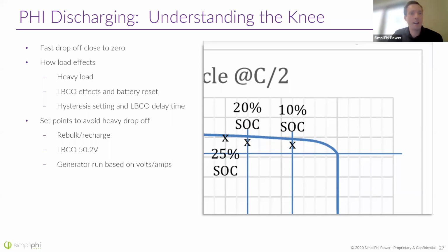Okay, low battery cutout effects. When you load a battery at a low state of charge, the internal resistance is increased for the reason I just told you, low density of carriers. So instead of seeing maybe a voltage drop of 1 volt for a surged battery, you might see a voltage drop of 2 volts, because the internal resistance of the battery changes with state of charge. That being the case, if you try to surge a battery at low state of charge, the battery might do a low battery cutout, or the equipment might do a low battery cutout, because the actual voltage of the battery, even though it's above 48, that 0% number, the battery is seeing a large drop due to the load. That's the internal resistance I was talking about.